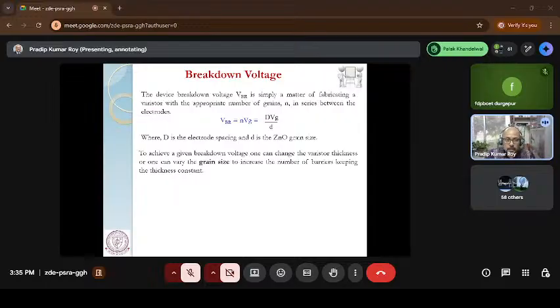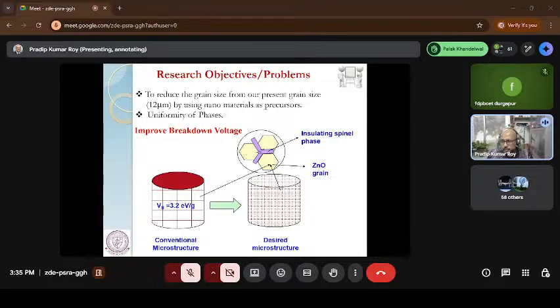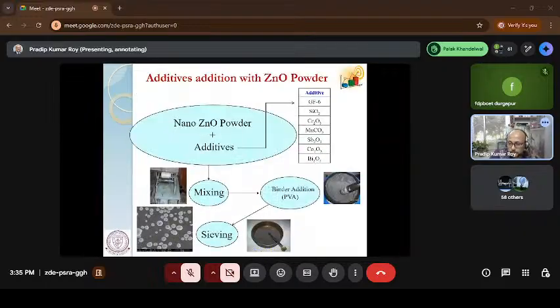Okay, so based on that, the research purpose has come. Normally it is found that the industry-produced product has a rating of around 140 volt per mm, and the grain size is around 12 micron. So if I reduce the grain size, definitely it will increase the breakdown voltage, and definitely it will increase the rating of the voltage. So for that purpose, as I said, 96% of the oxide material is actually zinc oxide. So we produce zinc oxide through a spray pyrolysis method, because it's an industrially commercial product. I am not showing all the data here, but still I'm talking about the spray pyrolysis method.